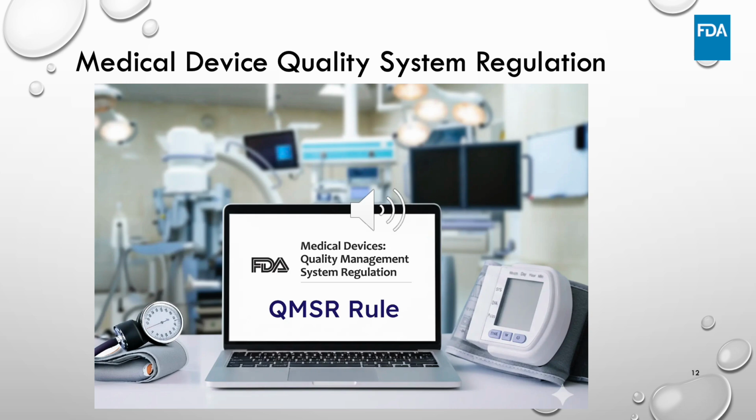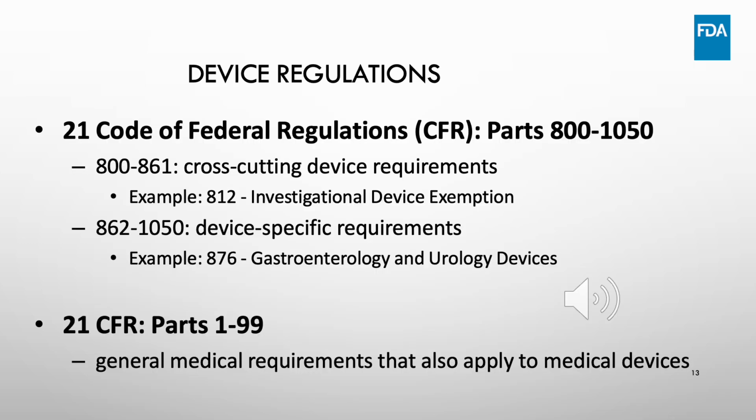The concept of TPLC is encoded in the Management of Medical Device Quality System Regulation. The QSR is considered a general control and applies to all medical devices regardless of class. Our federal laws are intentionally written to be broad.